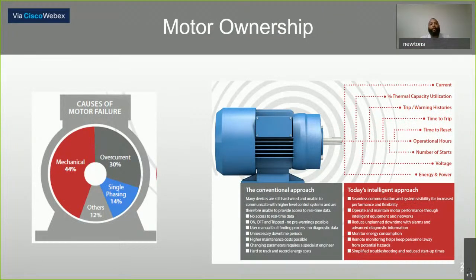So first and foremost, let's start with motor ownership. This is a really good graphic that outlines the typical causes of motor failure, and it divides it between mechanical, electrical, and other. 44% of your issues or motor failures are caused by mechanical issues. In that case, you will call your friendly mechanics from the mechanical shop to work on those issues. When it's not a mechanical issue, 44% of those times it'll be electrical. That 44% will comprise 30% overcurrent issues and 14% single phasing.